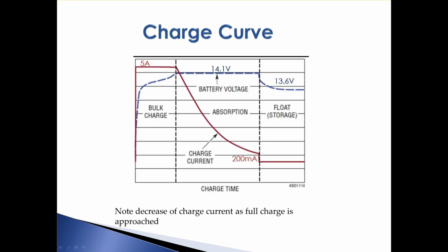The charging curve for a lead acid battery is very interesting because the typical charger will start off in some constant current mode when the battery is discharged, and it'll have some limiting voltage, which it'll get up to, which is set on the battery somewhere around 14.1 volts. And so when you first start charging the battery, you get a lot of current flowing, whatever the charger is set up to do. But as you approach that final voltage, all at once the battery simply will not accept the current. It basically is fighting back to the charger, and so you'd take a much longer time to get the last 20% than it took to get the first 80%.